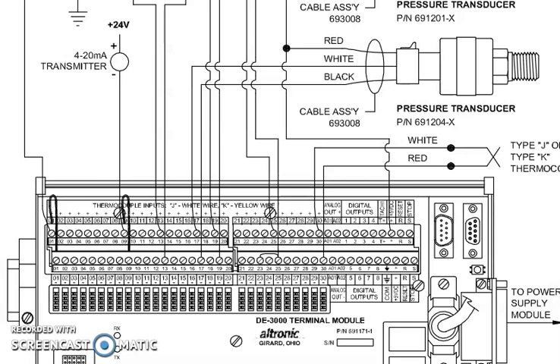Some of you may have watched the video on how to calibrate a 0 to 5 volt pressure transducer, but you were asking yourselves while you were watching, well, hey, I don't have 0 to 5 volt pressure transducers in my panel. I have 4 to 20 milliamp pressure transducers in my panel. That's great. We've got a way to do that too. So in today's video, we're going to cover how to calibrate a 4 to 20 milliamp pressure transducer.